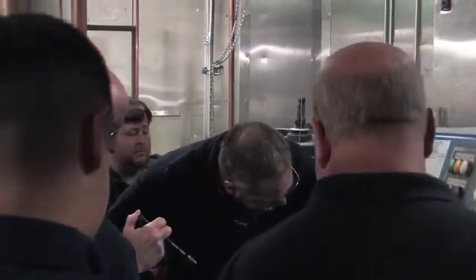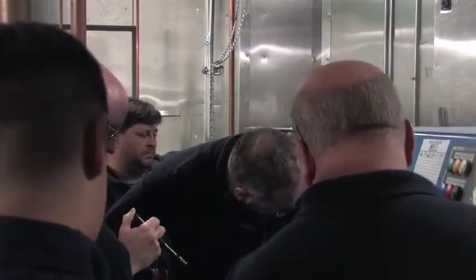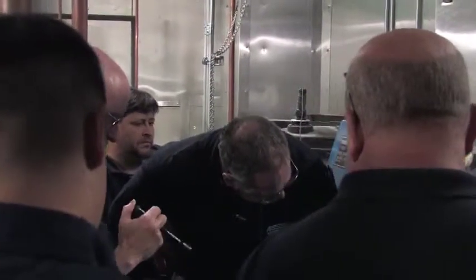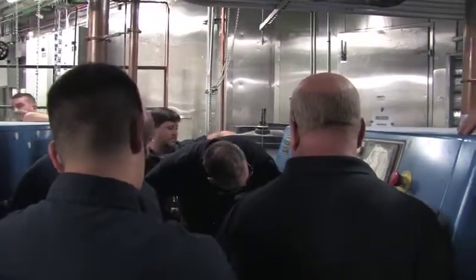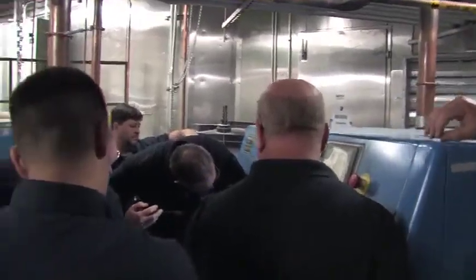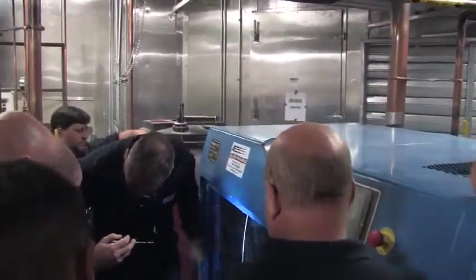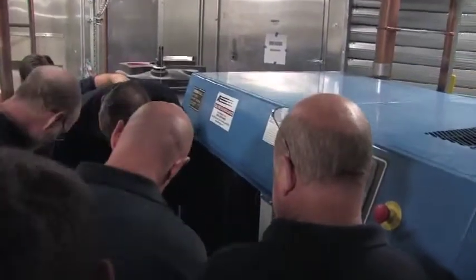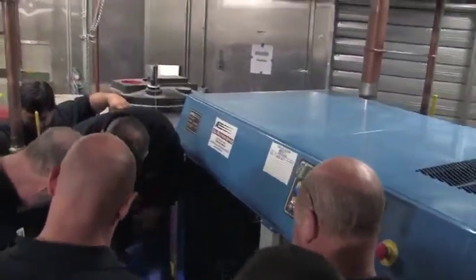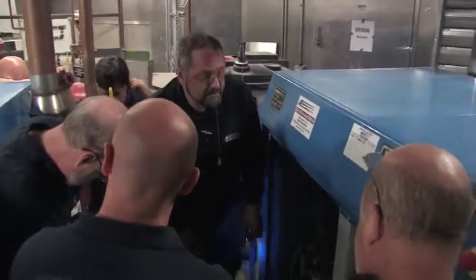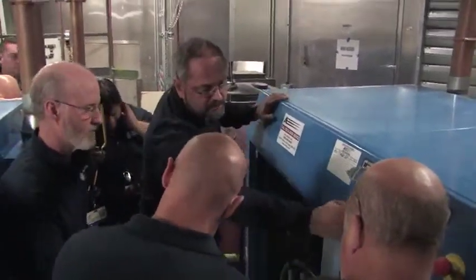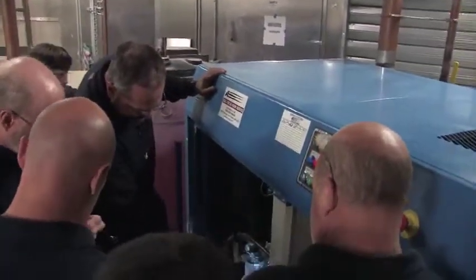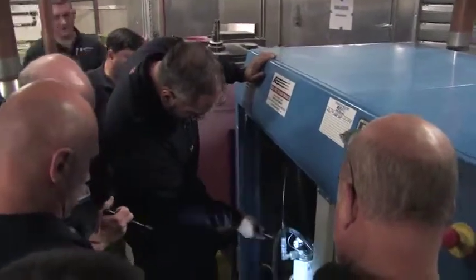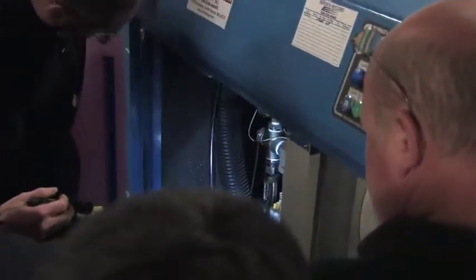So then your air comes back off that separator, goes into the second stage, gets compressed to the final pressure, goes to the aftercooler, and comes out of that and goes down, and the moisture separator for that is on the outside, where you can see it. Obviously, the things you're supposed to check every day are temperatures and pressures here. You're supposed to check that oil level. You're supposed to check that oil filter differential.